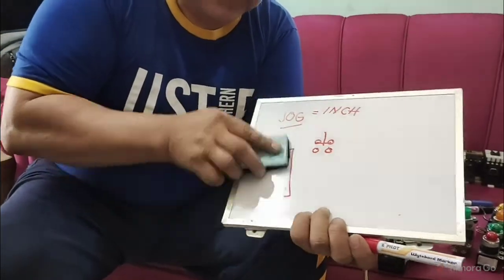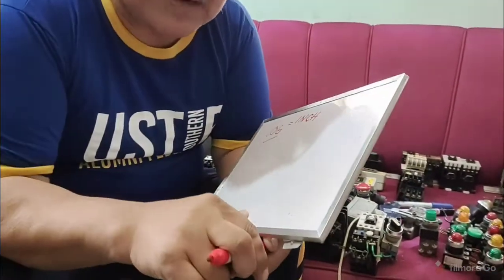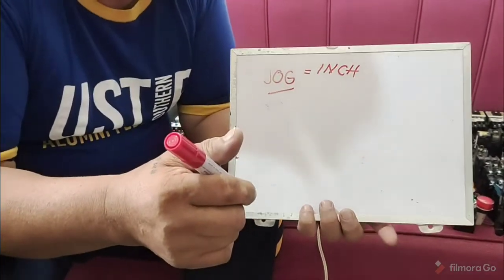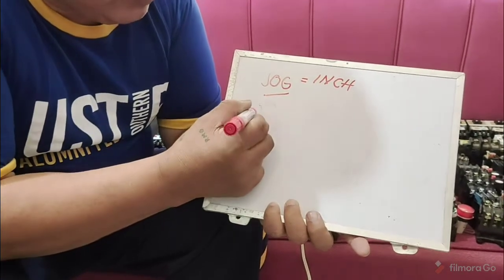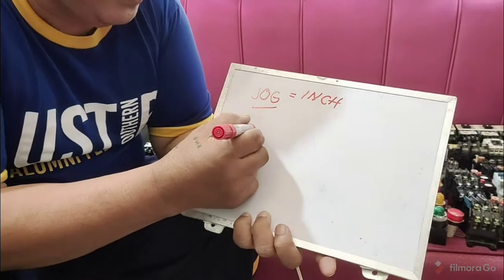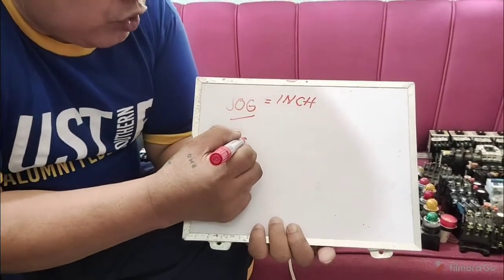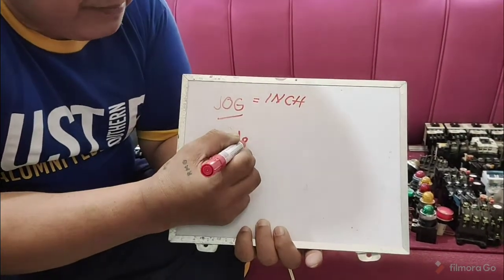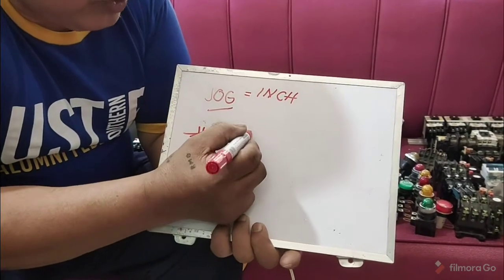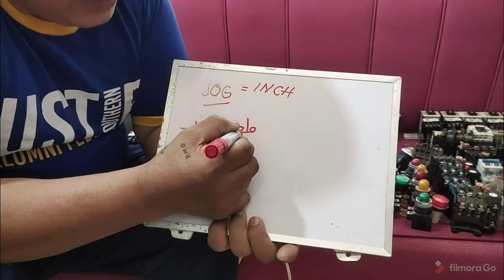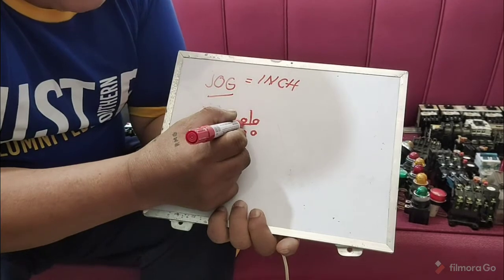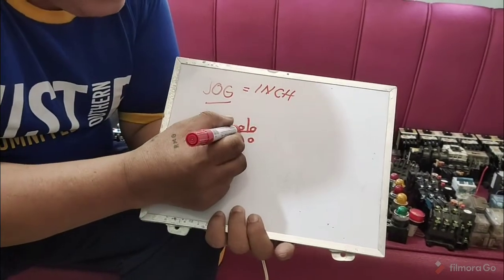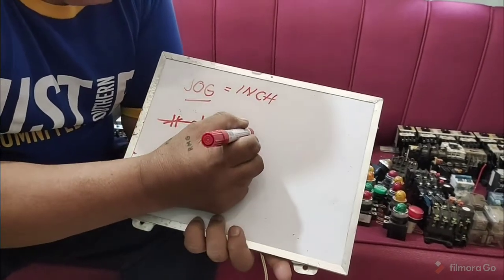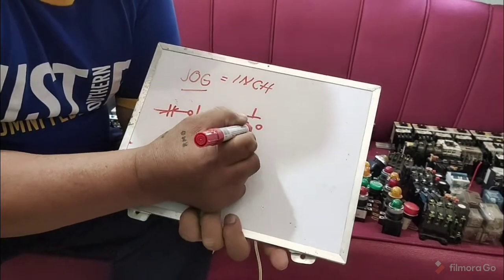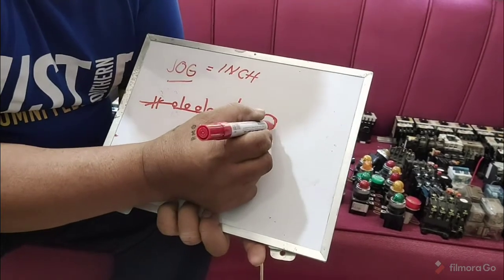Okay? Now, how would you connect this in the circuit? So like this. Still, this is under full voltage magnetic starter and direct online magnetic starter. So, you have your overload contact here coming from the overload relay, and then you have your push button stop like that. Then of course you have your jog button, then again that is double contact. Then since we learned that if that is normally closed, you connect that in series. Okay, then you have your start button, then you have your magnetic coil.